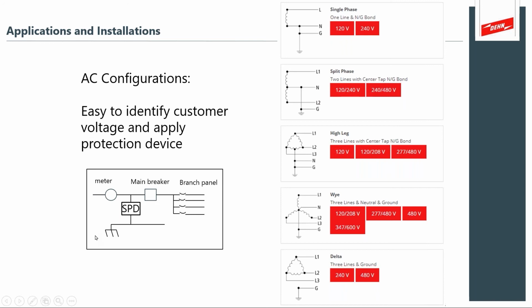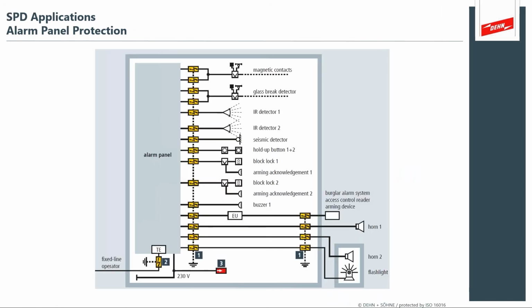So in this illustration, you can see that if there's a ground potential rise, your SPD will control that voltage between the earthing and your electrical service. But remember, downstream, you still want to apply coordinated surge protection devices.